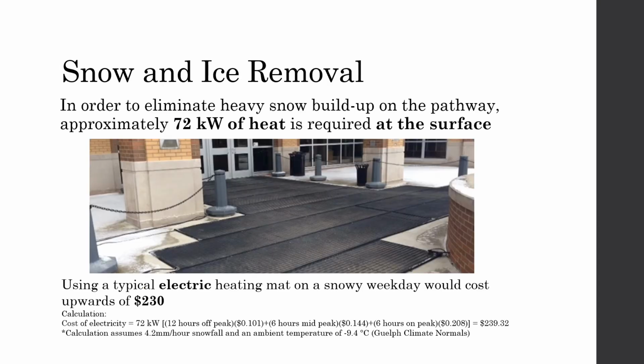The second design objective involved preventing snow and ice from accumulating without salt or people power. And we've considered traditional ways of using electrical energy or boiler heat to melt snow, but concluded that they were energy intensive and therefore costly to operate. For example, it would cost upwards of $230 a day to run an electric heater, based on current utility charges and Guelph's climate normals. So further brainstorming revealed an alternative that was cost-effective to operate and required virtually no maintenance.